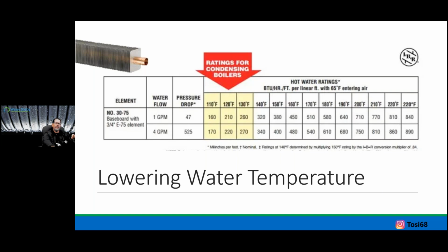What size copper is important because of flow? But here, if you look on this chart, there's a 3/4 inch copper, basic number 30, I believe this is Slant/Fin. So Slant/Fin makes a 30, they make a 15, a 30, they make an 80, you know? Why different numbers, different ratings? Not all BTU, not all baseboard is created equal.